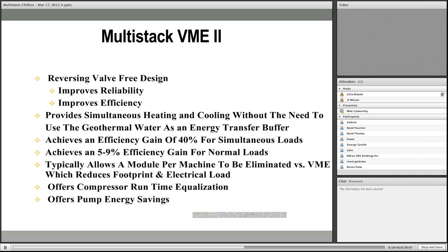VME1 was a system with reversing valves. Reversing valves cause pressure drop, and that takes efficiency and capacity from a refrigeration system. So we wanted to eliminate the reversing valve, and we wanted to maintain what's called counterflow.